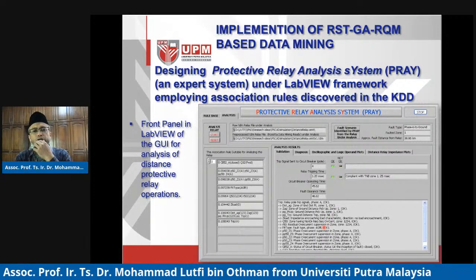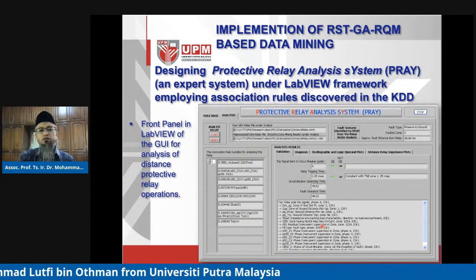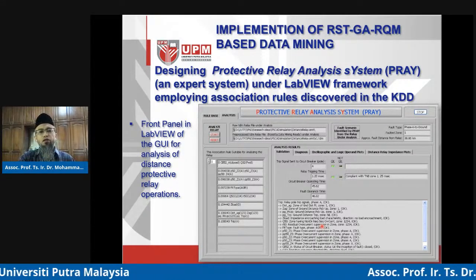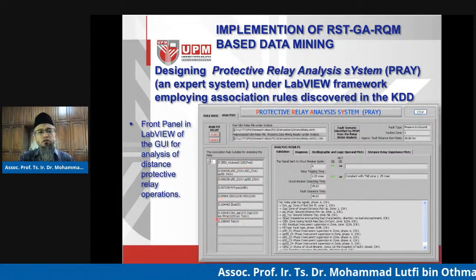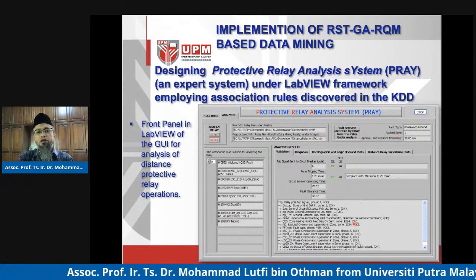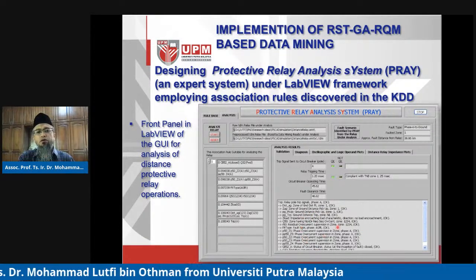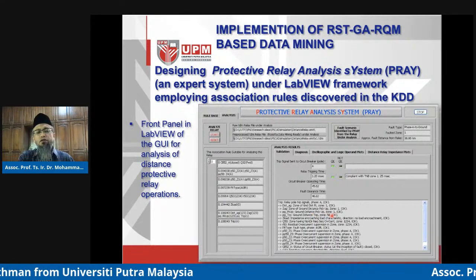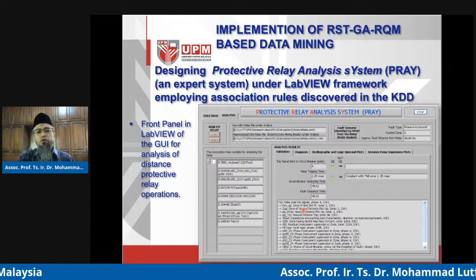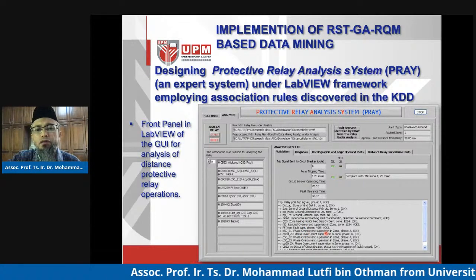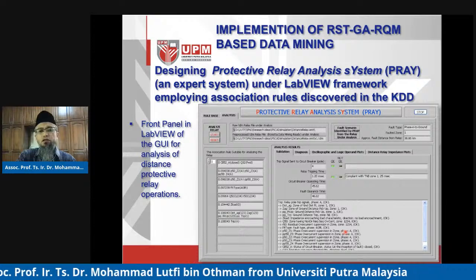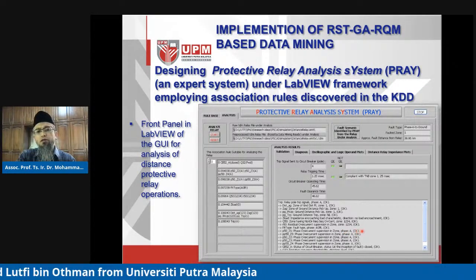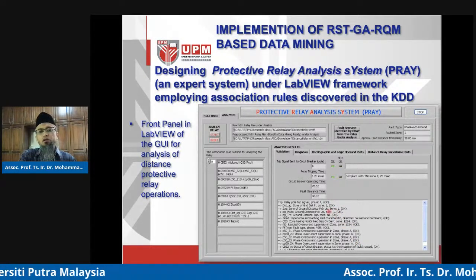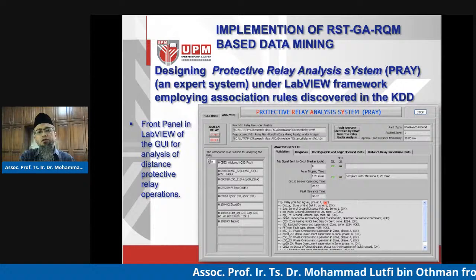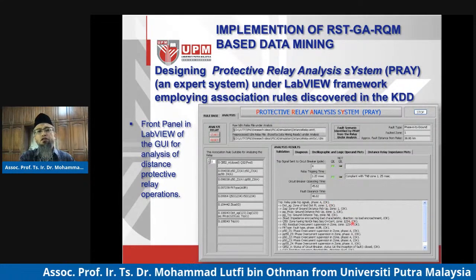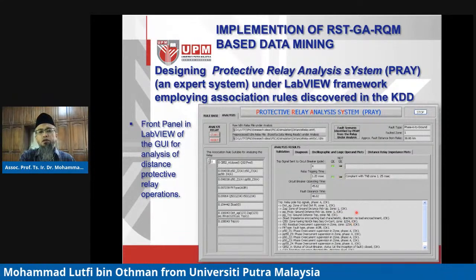So if you look at how the relay behaved internally across all these functional units, what the expert system does is compare these rules with the data extracted from the unknown relay, giving us information on how the functional units actually behaved. For example, the overcurrent supervision unit correctly operated to detect zone A, and it's okay, meaning functional. So finally, when all conditions are okay, we expect the tripping signal from the relay to be okay. This is a validated operation of the relay we are testing.